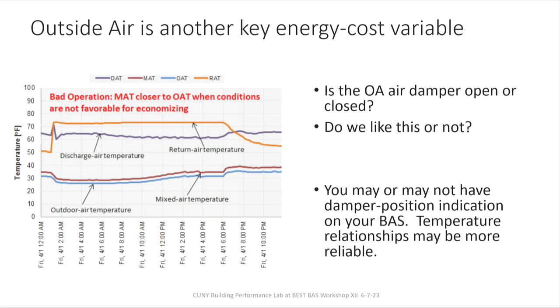Michael, can I point out two quick things on the trend here? There are two things here that I find particularly interesting. The fact that your mixed air and your outside air are so closely trending together. Obviously, we say damper stuck open, and I 100% agree. This difference in temperature could be real or it could be imagined. It could be a difference in the location of the outside air temperature sensor, or it could be an inaccuracy between the two sensors. And the truth may be that we're pulling in 100% outside air.